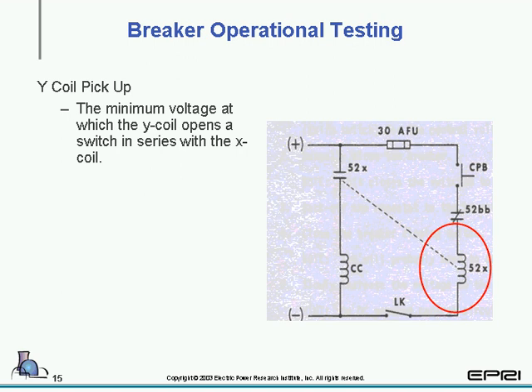Now the reason we're going to be taking a look at the Y coil is this particular coil can have voltage for extended periods of time, and it is your anti-pump circuit. In other words, this particular coil allows one attempt to close at a time.